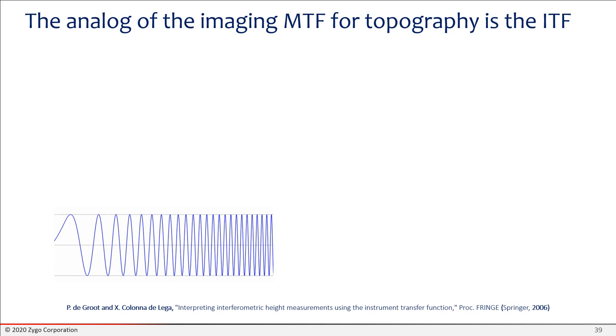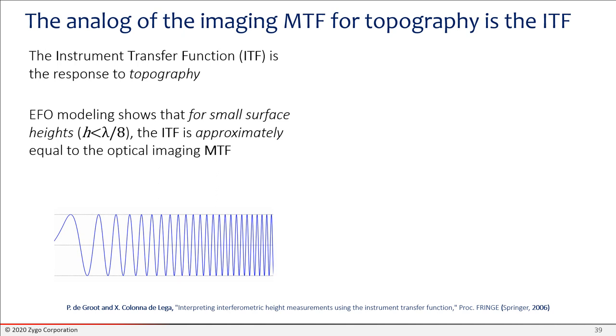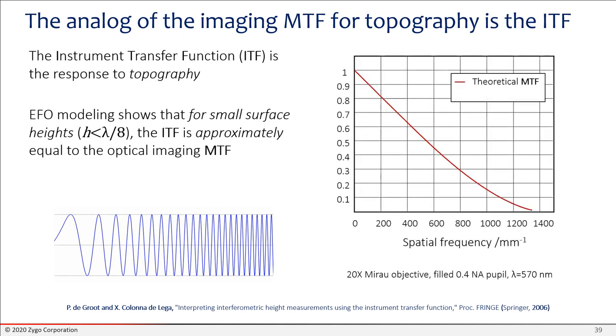The analog of the imaging modulation transfer function for surface topography is the instrument transfer function. So if the system is linear, you can use this instrument transfer function. That tells you how the interferometer, the measuring instrument, will respond to topography variations. Now what we found is with the EFO, if you have small surface height variations, then the ITF is approximately equal to the optical imaging MTF. So this was shown some years ago, and it's a nice result because it means that if you calculate the theoretical MTF, you have a fair idea of what the transfer function characteristics are going to be of your interferometer. So this compares the measured ITF, what is actually measured on the instrument as the response characteristics compared to this theoretical MTF, and you can see they follow each other quite closely, again for small surface heights.